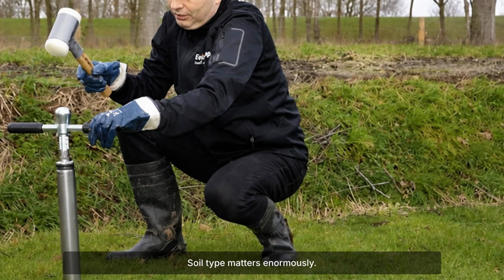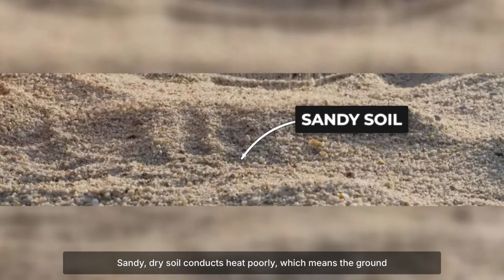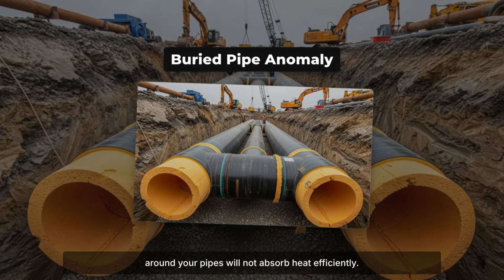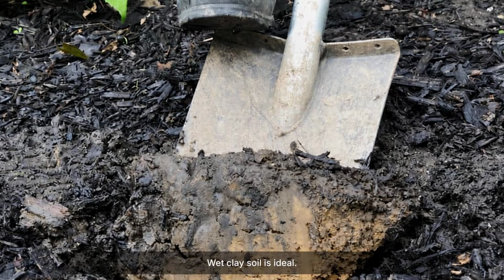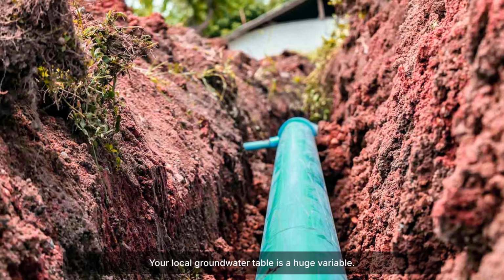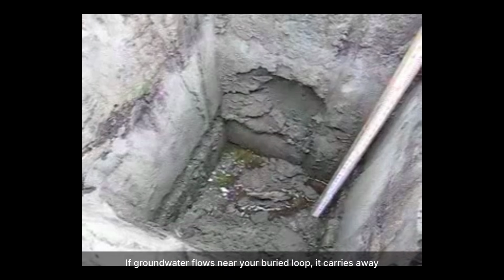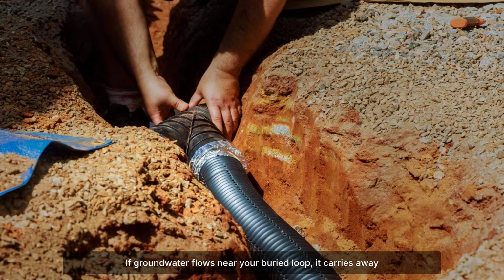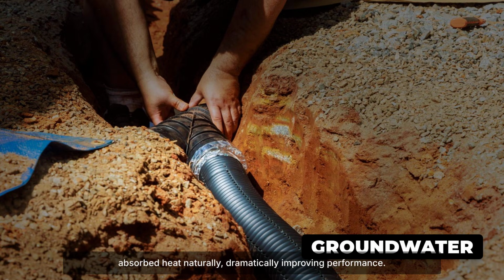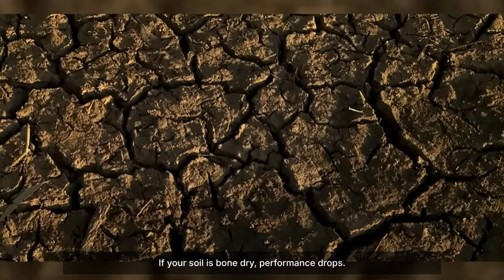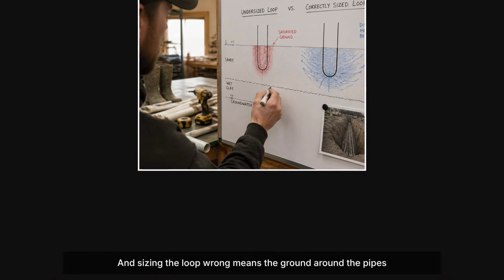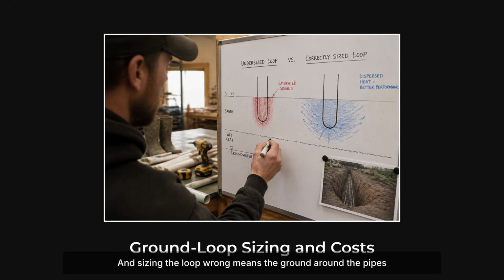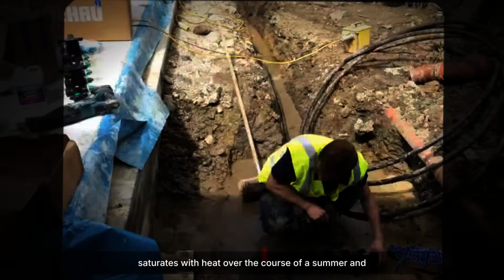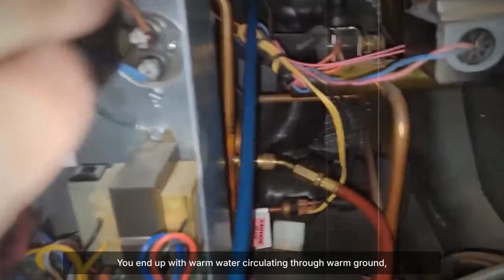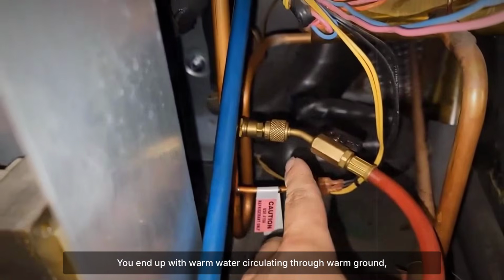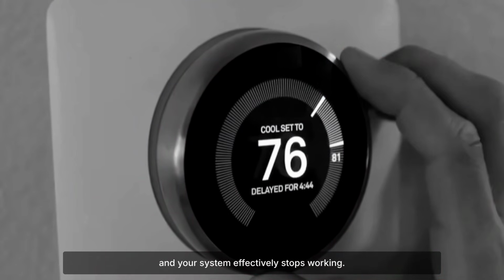Soil type matters enormously. Sandy, dry soil conducts heat poorly, which means the ground around your pipes will not absorb heat efficiently. Wet clay soil is ideal. Your local groundwater table is a huge variable. If groundwater flows near your buried loop, it carries away absorbed heat naturally, dramatically improving performance. If your soil is bone dry, performance drops. And sizing the loop wrong means the ground around the pipes saturates with heat over the course of a summer and gradually stops absorbing. You end up with warm water circulating through warm ground, and your system effectively stops working.